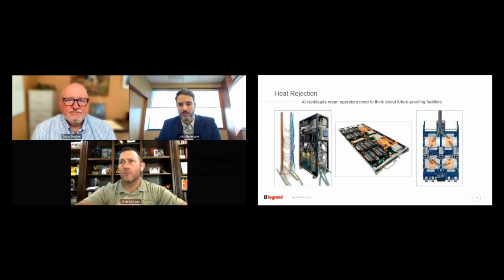The thing that we're finding with these chip level cooling systems is that they're being advertised at 100% capture. And when you peel back the layers of the onion, they're more like 90%. When you peel back a little bit more, they're more like 70%. And so we're doing something that's new and different, but at the same time, you still have to do perimeter cooling or some sort of other supplemental cooling, because number one, you still have network components that aren't going to get the chip level cooling. So you're still going to have latent heat that goes into the room that you still have to deal with from a design and construction and operation standpoint.